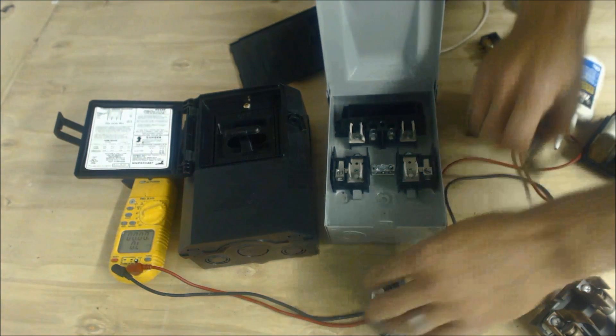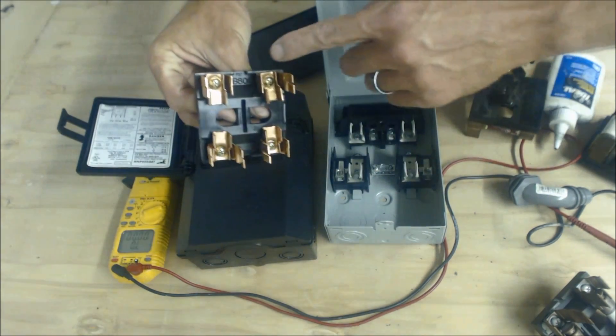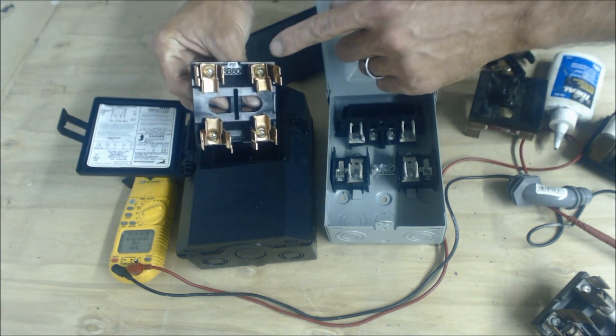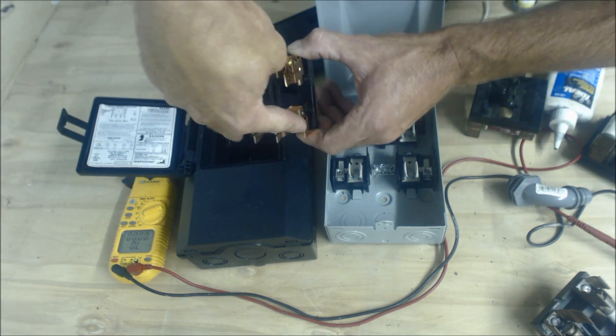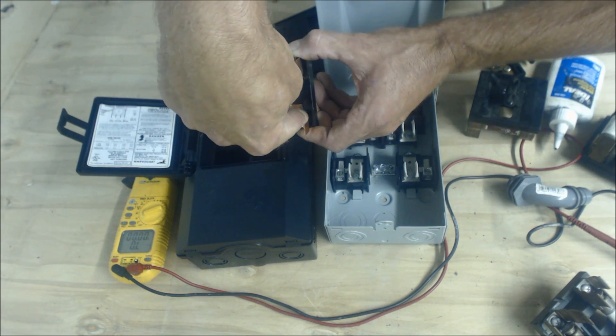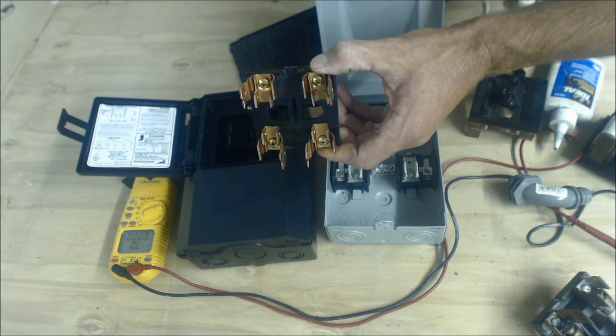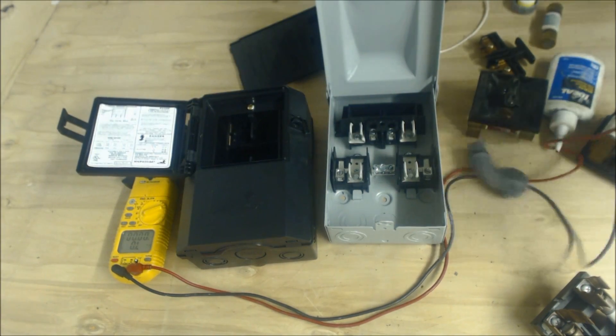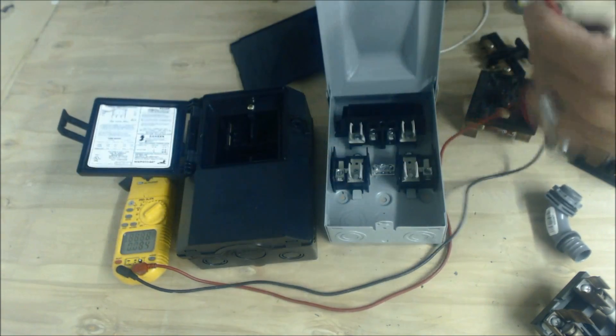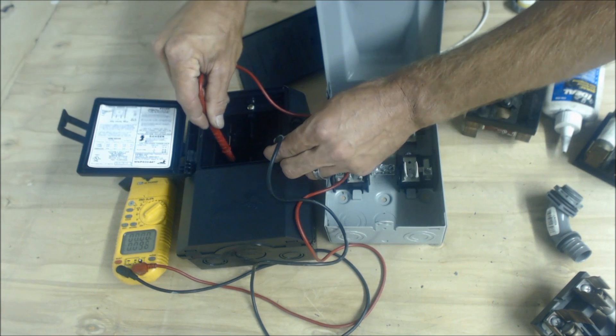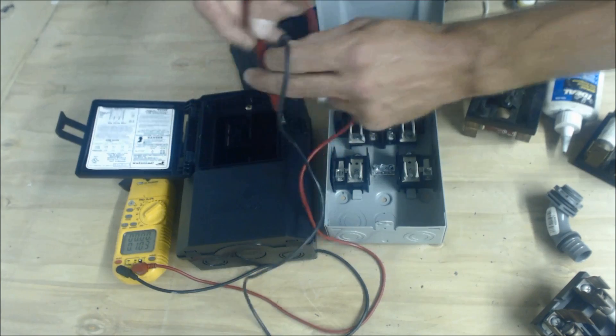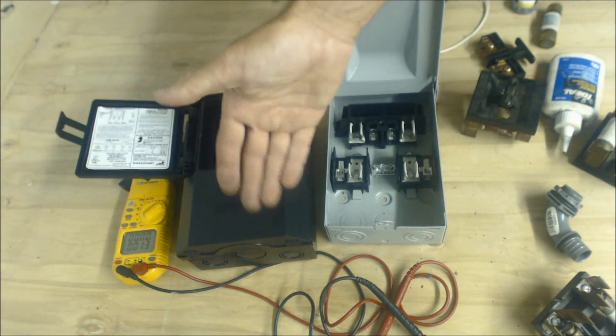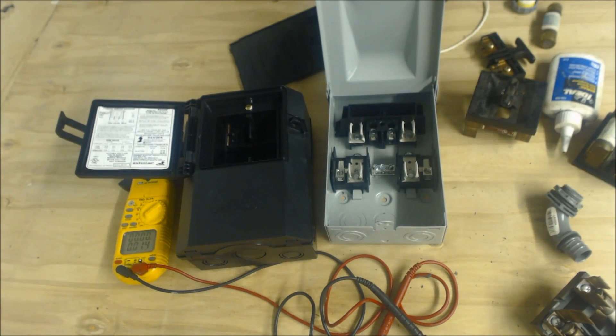But in the case of a disconnect like this, what you're doing is when you're trying to read voltages, you know that when you're going up and down, your electrical connections are touching here and here. So basically, what you do know is your power's coming in from the bottom or your power's coming in from the top, depending on the make of the manufacturer right here. So you're going to put your probes here, you're going to put your probes here inside this electrical disconnect. So if we turn this to volts right here, we can come into the electrical box and read it like this, or we can come up here and read these electrical connections. And if we don't have 240 volts, then we've got to find where our problem is. And if it leads back to the breaker box, unless you have an electrical license, you should be calling an electrician.